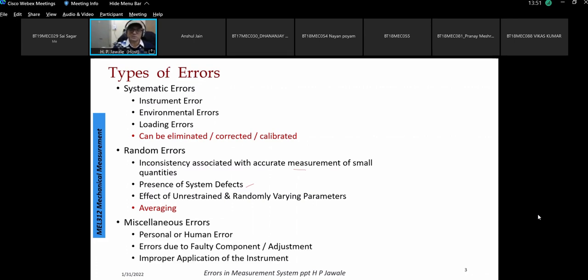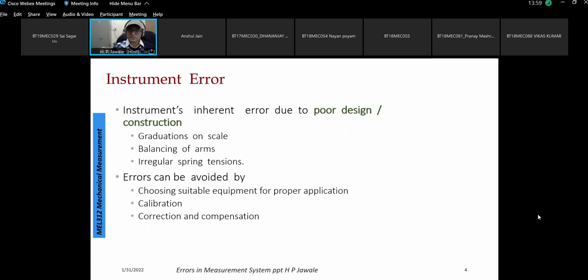Let us understand the types of error. We've gone through this in the last lecture in detail - systematic error: instrument inherent error due to poor design, construction, configuration, and improper staging into the measurement system. It may be because of graduation of the scale, balancing of the arm, or irregular spring tensions.